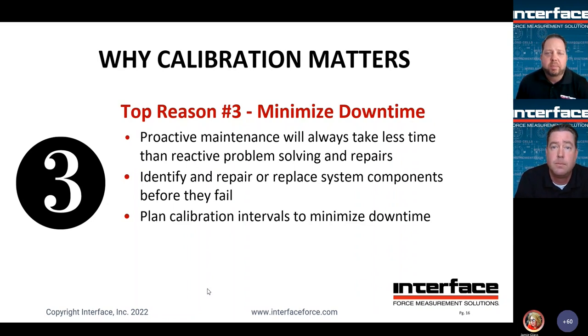Next one's minimize downtime. You want to be able to do perhaps proactive maintenance on a machine, on an article. Therefore, having good calibration around that will allow you to take care of things before they start to fail. So if you're doing periodic checks, whether it's a material test frame, to ensure that it stays within spec or that it stays performing as you expect, you can then do your planned calibration intervals and minimize the downtime. Next.